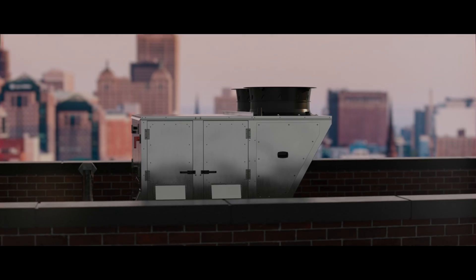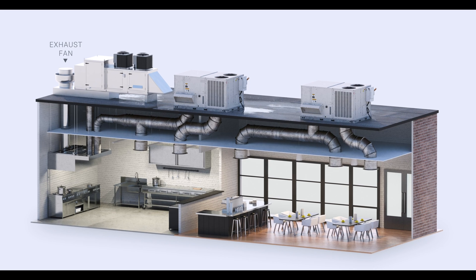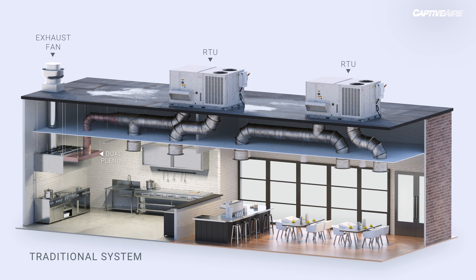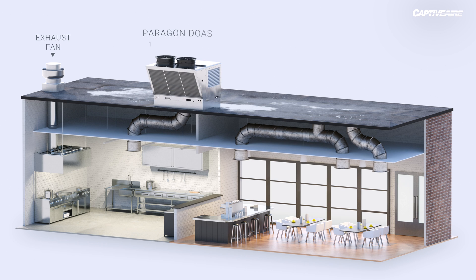DOAS has caused one of the biggest changes in the restaurant ventilation industry that I can remember. We took a step back and looked at the overall kitchen and basically had multiple units on the roof doing the same exact thing. So our idea was to eliminate the makeup air unit, eliminate the makeup air plenum, eliminate the return duct in the kitchen and the RTUs, and replace all that overlapping technology with a DOAS unit on the kitchen and another DOAS unit on the dining room.